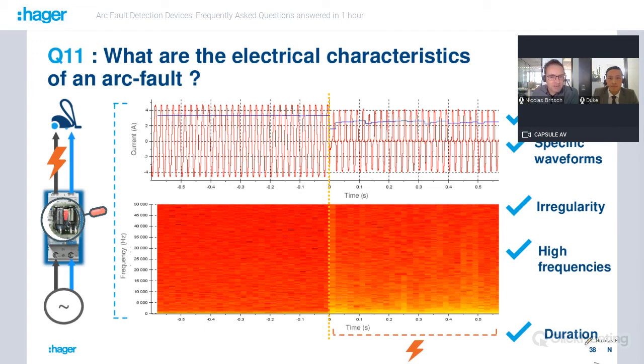So what are the electrical characteristics of an arc fault? Here is an example of series arc fault recording. The first graphic on the top is the current signal as a function of the time, and the second graphic on the bottom is a spectrogram of the current. And there are 5 important electrical characteristics related to arc faults. The RMS value of the signal, as explained before, has to be greater than 2.5 amp.